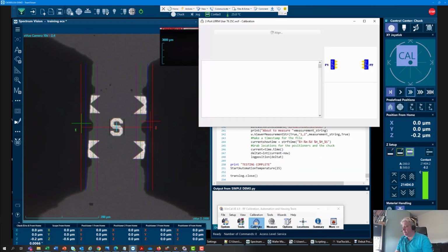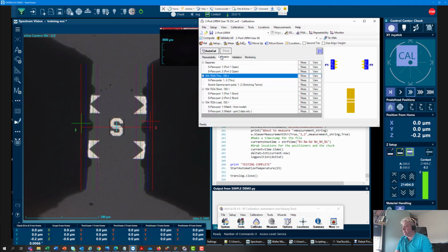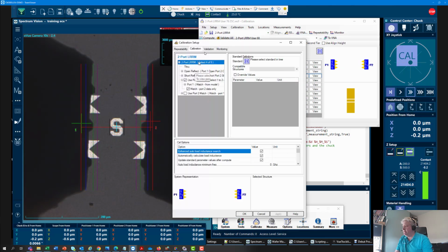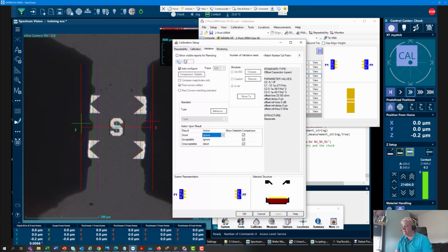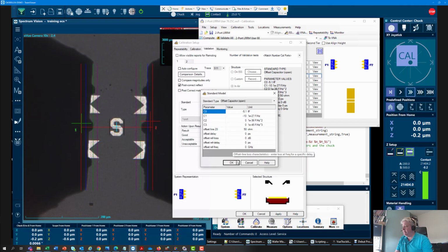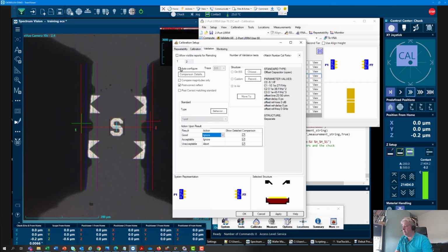Calibration. Autonomous will use whatever calibration algorithm we have set up. We have the LRRM calibration set up. We're currently set up with an auto-load inductance calculation range of 0 to 120 gigahertz, and we're going to use enhanced auto-load inductance calculation. And what else to say? Validation. We're going to be using the automatic settings to validate with, which you see the behavior in here. If I turn this off, you'll see the behavior. So minus 5.1, minus 10 femtofarads on the capacitor. This post-correct reflect means it will be correcting using the open it measured during the cal.